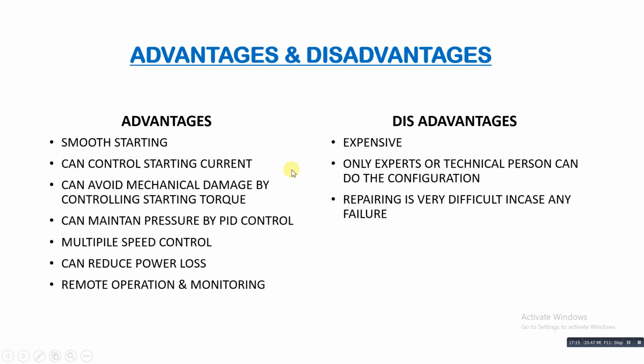Now we will see the advantages and disadvantages of these VFDs. First we will see the advantages. As I already told, you can do smooth starting. You can control the starting current with this VFD. You can avoid mechanical damage by controlling the starting torque. In this VFD, direct PID control is available. With this PID control you can maintain a certain pressure in your industry or your application. So you can run your equipment at different speeds, 0 to full speed, whatever speed you like, you can control your equipment. By using this VFD you can also reduce the power loss.